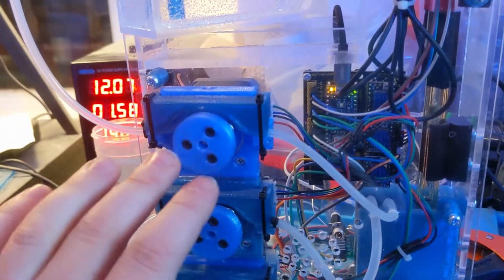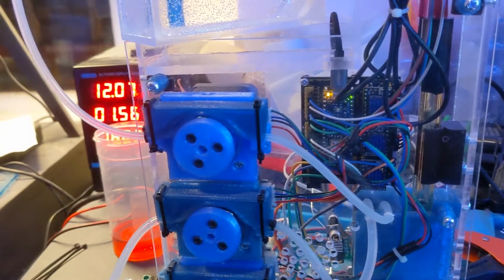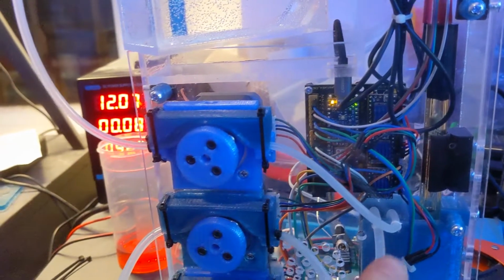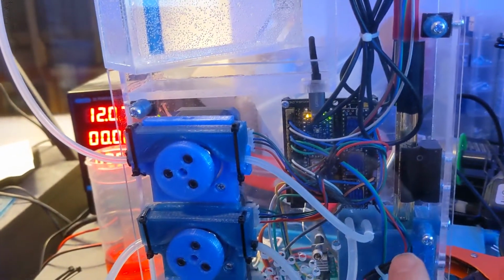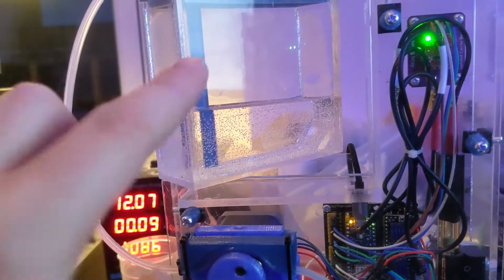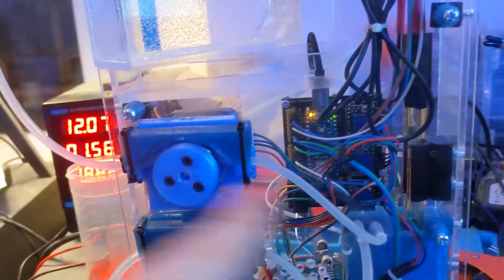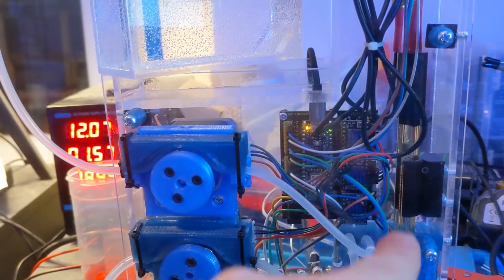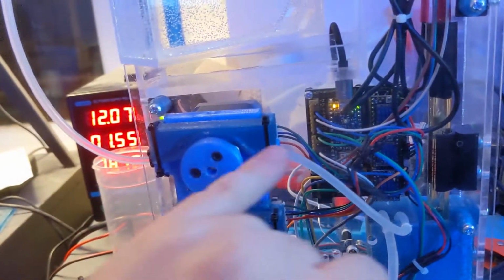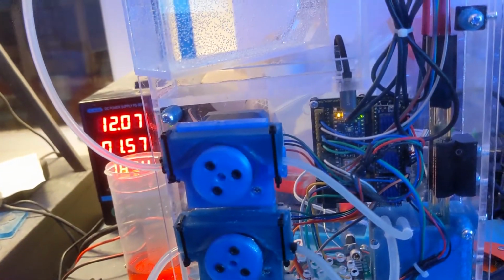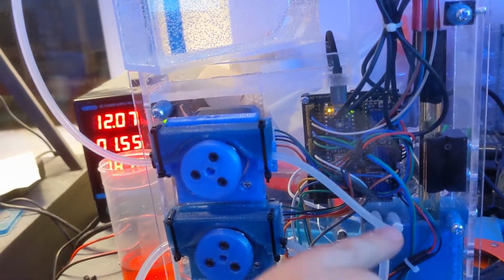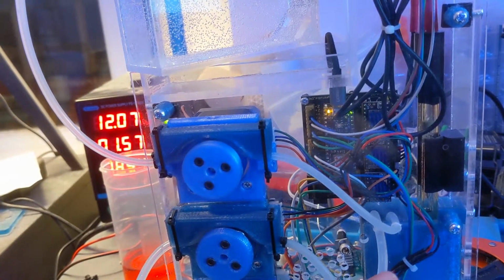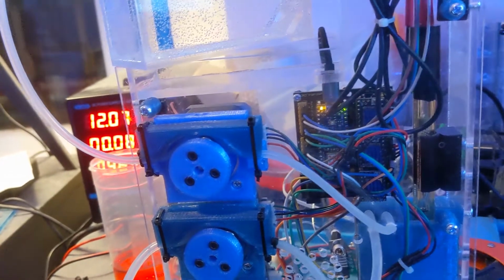What you're seeing it do here now is it's actually running the reagent backwards. So what happens is when it doses, if it leaves the fluid in the line, then because the storage chamber is above here, once the USB cable's not hooked in, it'll just sit in this top corner. Because it's above the reaction chamber, once that line is filled with water, it will continue to flow downwards because of gravity, even when the pump's not running. So after each dose, it runs backwards just enough to empty out that line, and then it runs it back forwards by that same amount before the next dose, before it starts counting how much it's putting through.